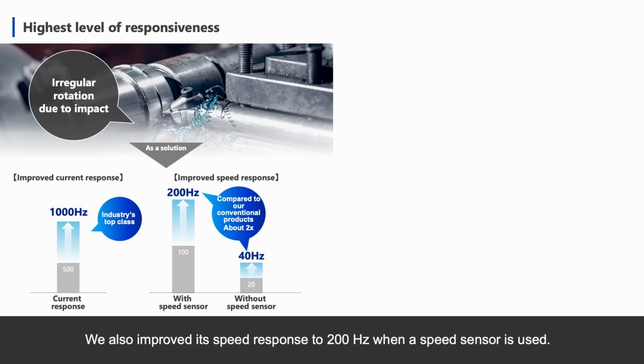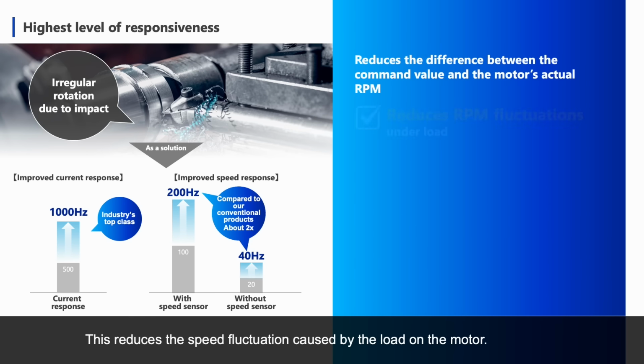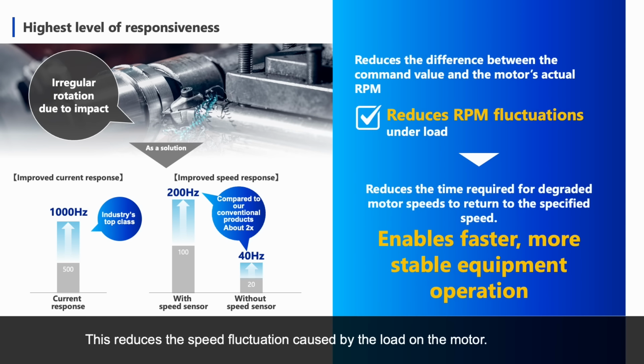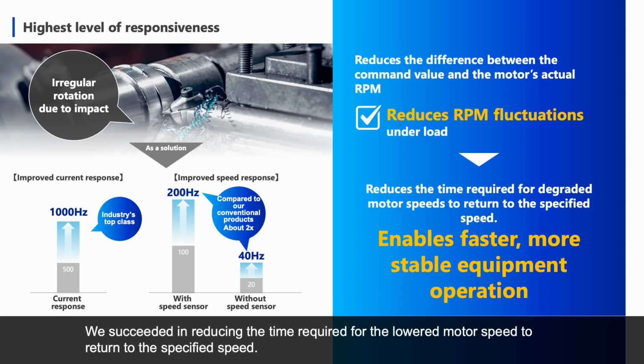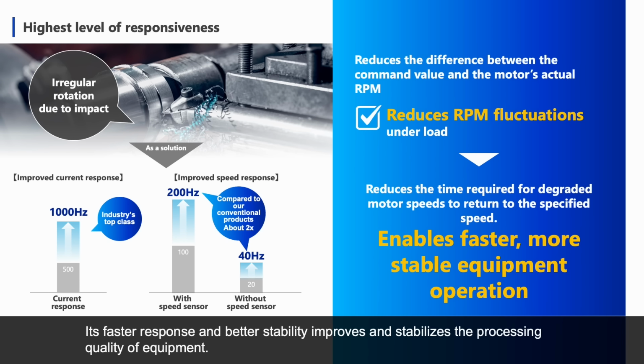We also improved its speed response to 200 Hz when a speed sensor is used. It also achieves approximately twice the performance of conventional products. This reduces the speed fluctuation caused by the load on the motor. We succeeded in reducing the time required for the lowered motor speed to return to the specified speed. Its faster response and better stability improves and stabilizes the processing quality of equipment.